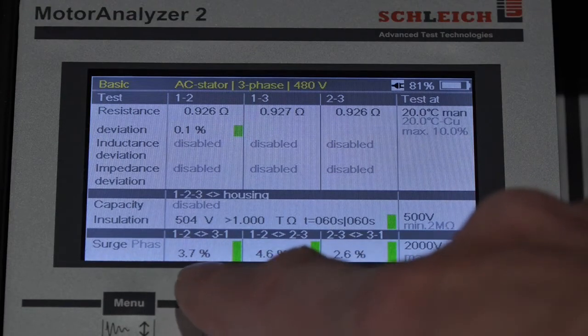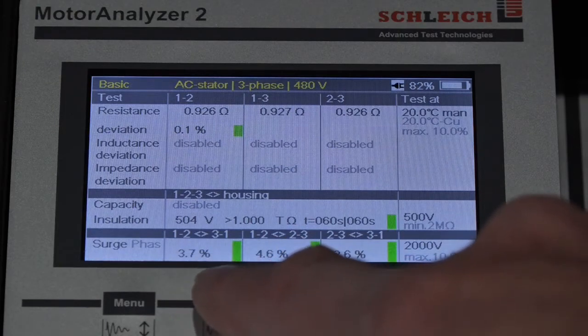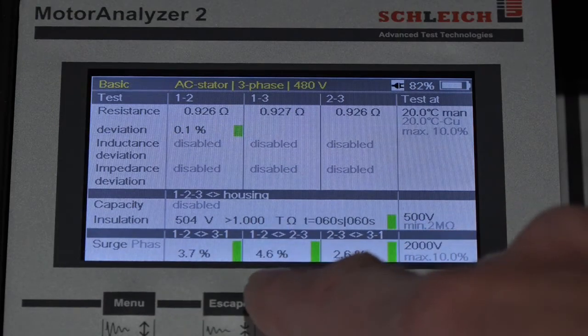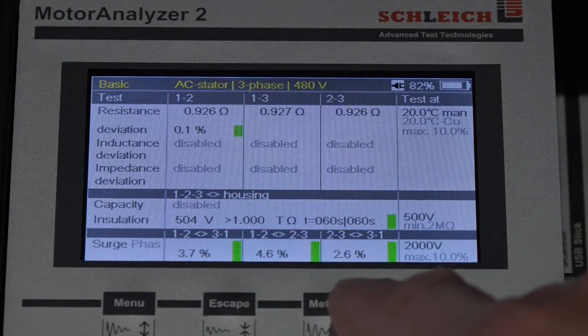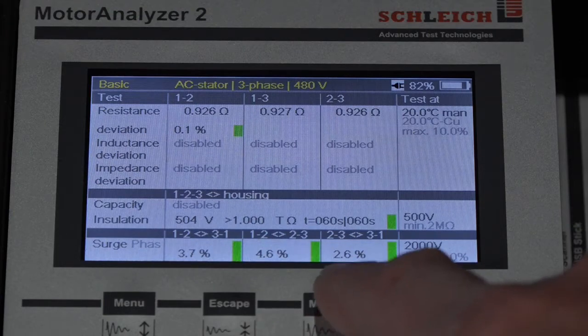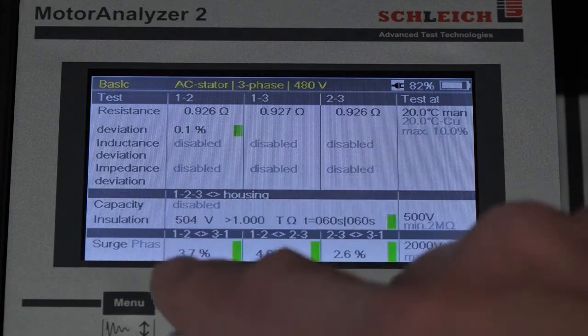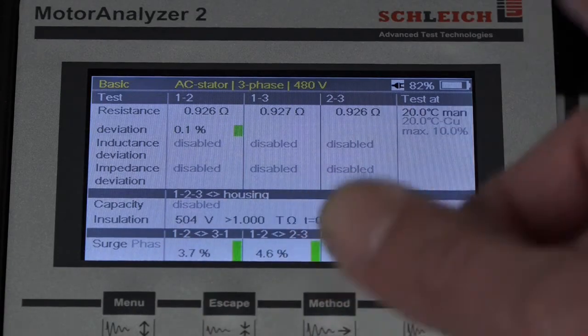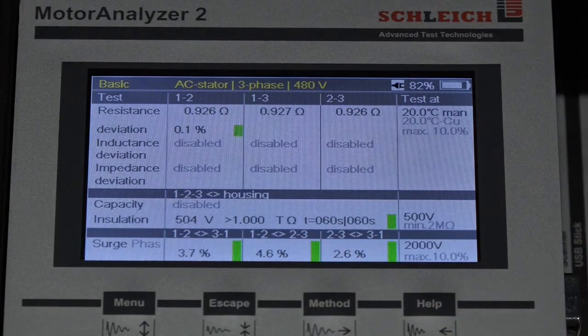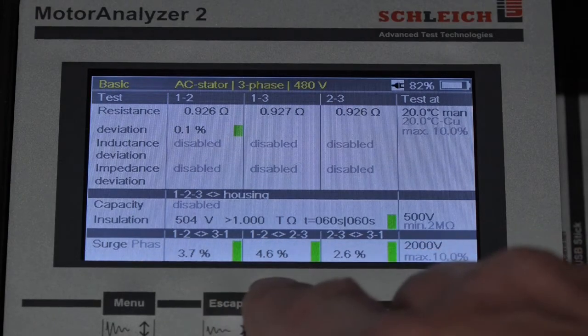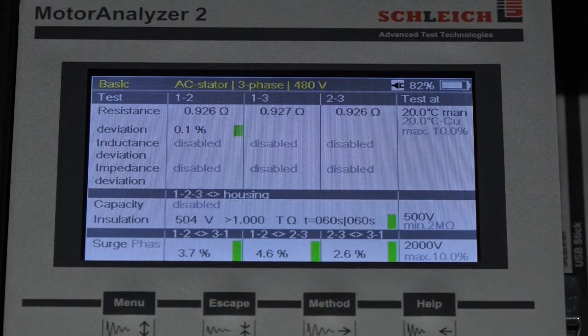So this 3.7%, that's the error area ratio between the waveforms obtained between testing between leads 1 and 2 and between 3 and 1. The 4.6% is for the 2 waveforms obtained between testing 1 to 2 and 2 to 3. And this 2.6% is the comparison of the waveforms between testing 2 to 3 and 3 to 1. So we don't actually have the waveforms in front of us right now. We'll go look at them in a moment. But we're getting the quantitative measure of the difference between the shapes of those 3 waveforms. The 3.7, the 4.6, and 2.6.